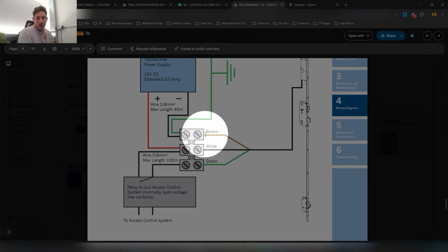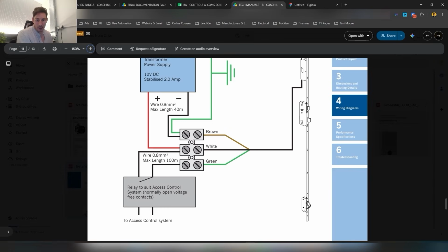We think about these as the terminal blocks, because this cable here is fixed to the lock, so we're going to have some Wago-style terminal blocks out in the field. One step past this, we've got terminal blocks going in here providing the positive, negative 12 volt DC. What we've just done here, we imagine this is the relay from the mini server - these are our purple cables, so we're getting that 12 volt constant feed here, and once we trigger the lock to open or close, however it's configured, this closes and sends that 12 volts out into the field, connecting to this green cable that is connected to the lock.